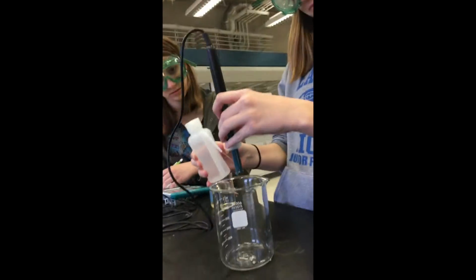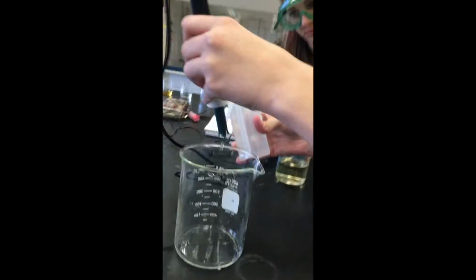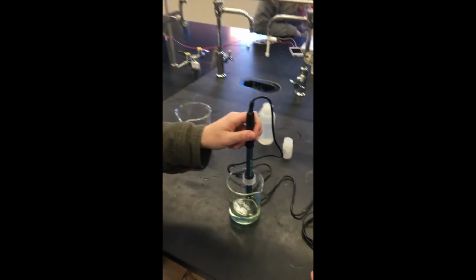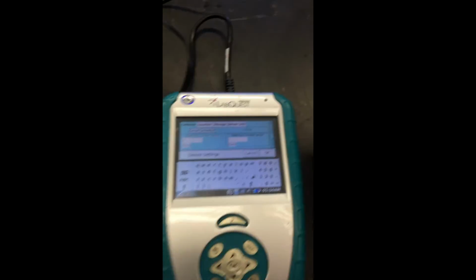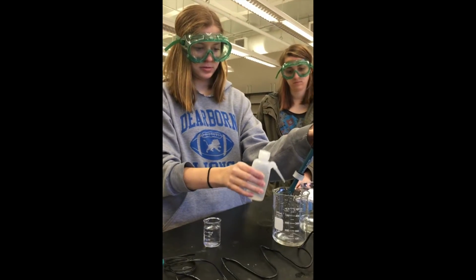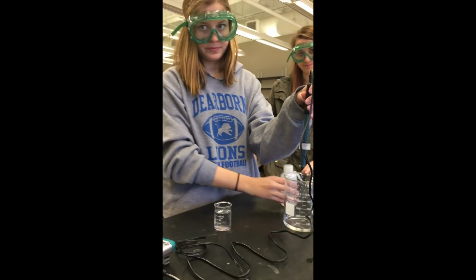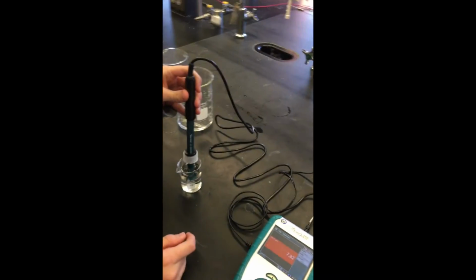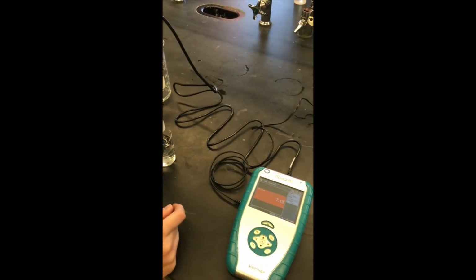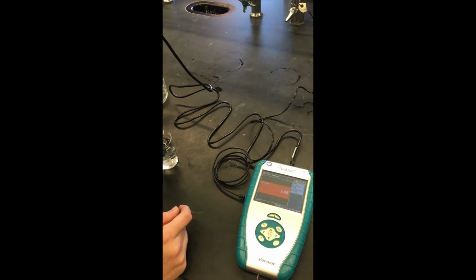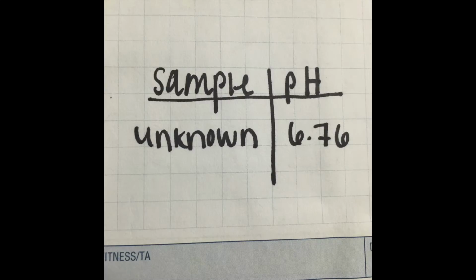Clean the probe with distilled water again. You will now repeat the same steps, but this time using buffer 7. Press 7 when storing. Now that your pH meter is calibrated, clean it off with distilled water again, and place the probe in the unknown solution. The pH of your unknown solution will be shown in the red box on the screen of your pH meter. Make sure you record your pH using correct significant figures in your data table.